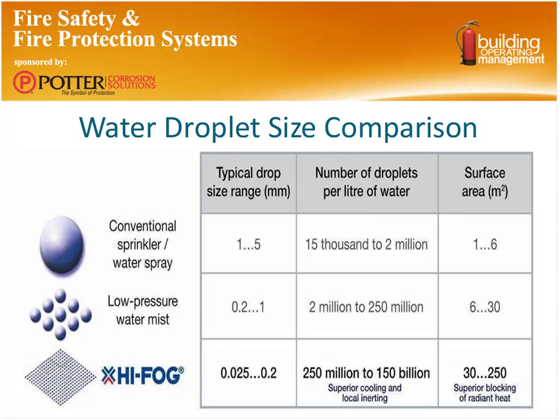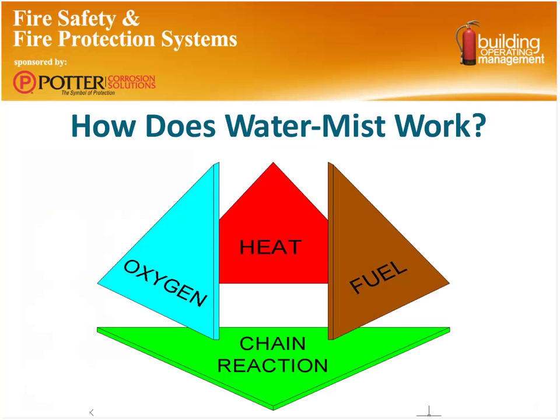If you were to be in a discharge of a typical sprinkler system, you'd definitely be a wet person very fast. In a fine high pressure water mist, what you'd actually feel like is like you were standing outside on a very foggy day, and you feel damp, your clothes are moist, but there's not water running off everywhere. It's not to that point. So how does fine water mist work, or how does water mist in general work? Well, to stop a fire, what we really need to do is try to remove some of these elements of the typical fire triangle: your oxygen, your heat, your fuel, and stop that chain reaction.